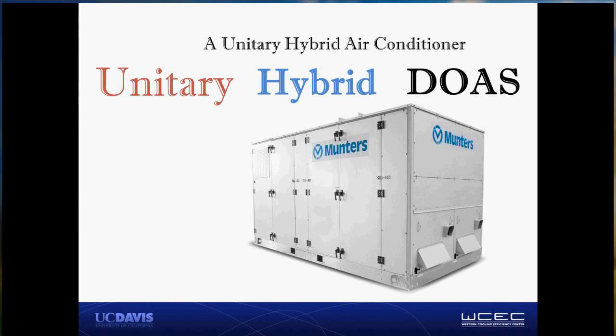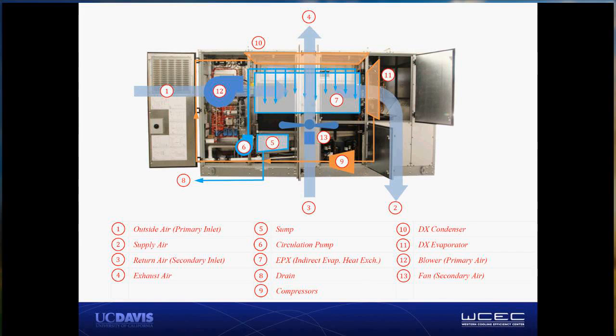It is a unitary hybrid dedicated outdoor air supply system that incorporates indirect evaporative cooling with vapor compression. Here's a good outline for how the equipment works. It's designed to bring in a continuous and steady supply of fresh outside air to provide for all of the ventilation needs in the store. That comes through a fan and passes through the dry channels of the indirect evaporative heat exchanger. When indirect evaporative cooling is enough to cover all of the room cooling loads, that's the only mode the equipment will operate in, and supply air passes to the space.